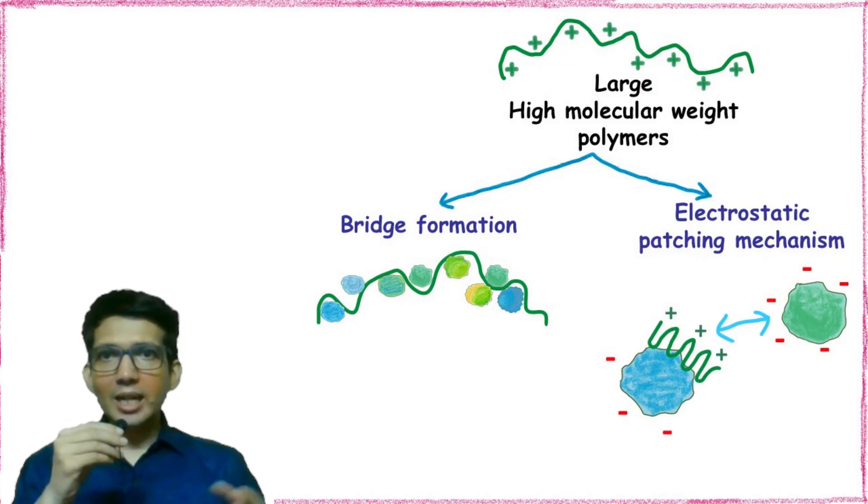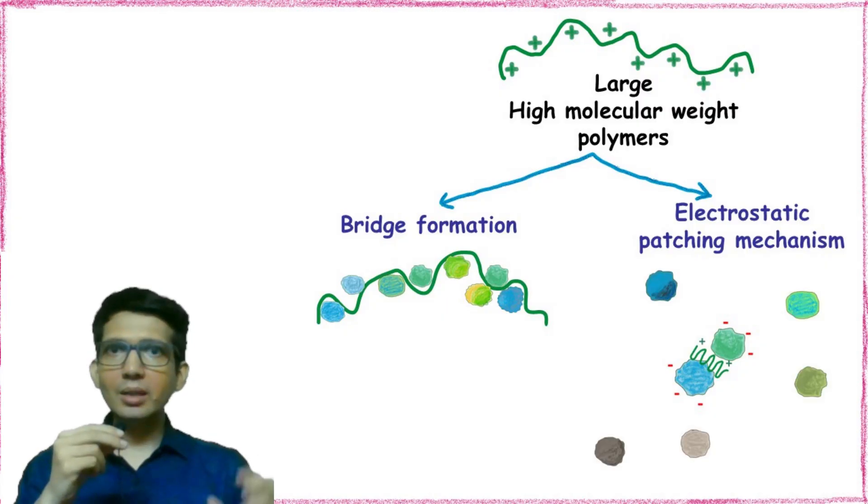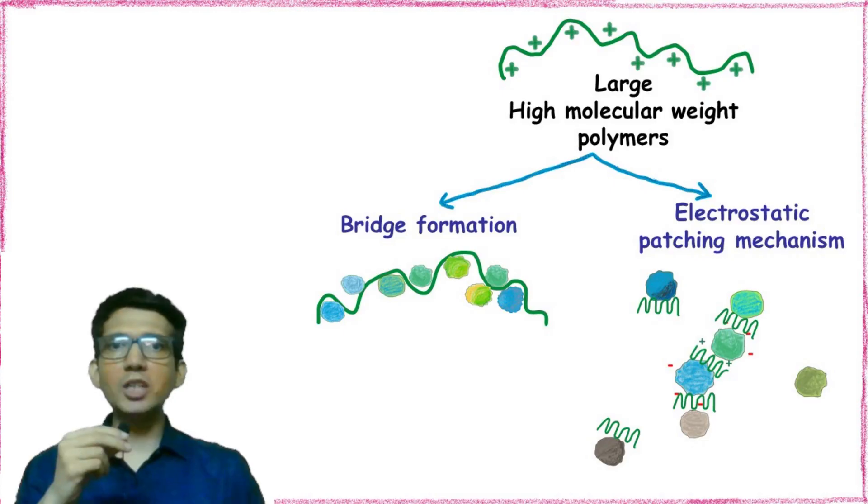In electrostatic patching mechanism, the polymer binds a small portion of the particle. This binding neutralizes the charge on the particle. Now the polymer bound with the particle attracts the other particle because of opposite charge. This phenomenon keeps on repeating until it results in formation of large flocs which easily settle down.